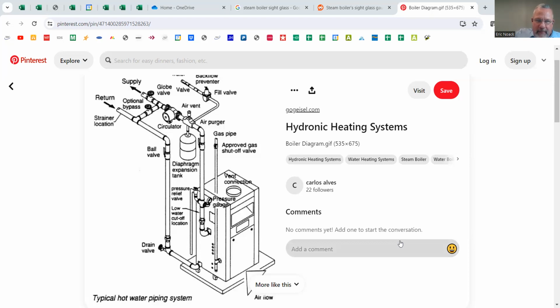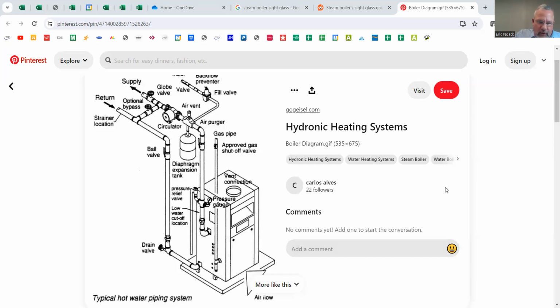So thinking about the main pipes that go in and out of the boiler, the return pipe is going to be at the bottom, right? The colder water, and we say colder, but it's not cold per se, but the coldest water is going to go into the bottom of the boiler, heat up, and then be pulled out at the top of the water jacket here. So the higher pipe is typically going to be the supply side. Most people like to have the circulator on the supply side, right? You like to push the water through the system rather than pulling it back. Again, there's some debate there. Some people say it's better to have it on the cooler side, the pump lasts longer, and so on. I don't know, but I see them on the supply side most often.